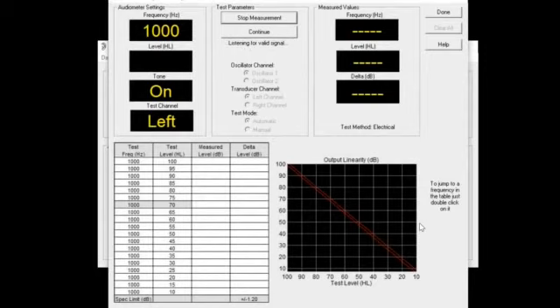Well, here we are in linearity, and we're on to the left ear. We start out at 70 dB, the maximum output of the audiometer, which is a manufacturer specification again, and start going down in steps of 5 dB. Now, if you want to change the steps that you're using or the intensity, that's fine. Program it into the system. That's what that selection of modifying the test pattern was all about. But it's not according to ANSI standards. Like I said, this is manufacturer's specification. The ACS program was used in the manufacturing of this 608.